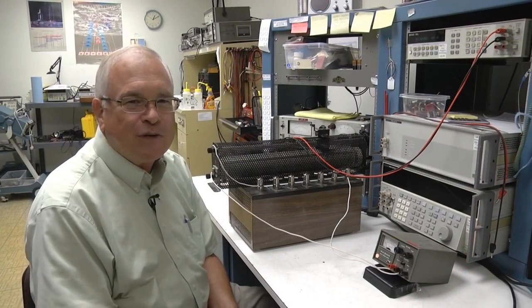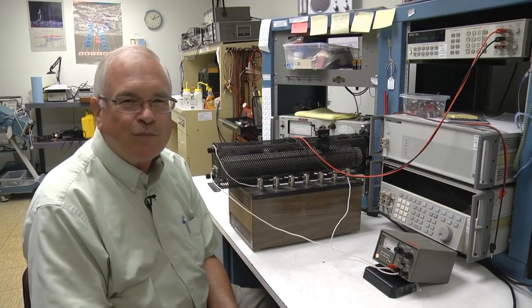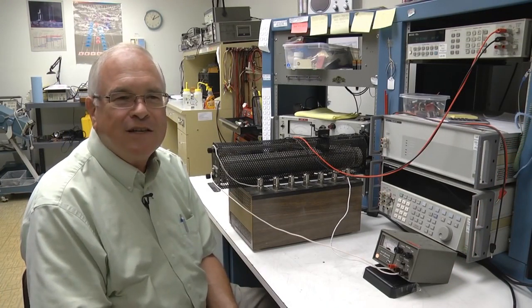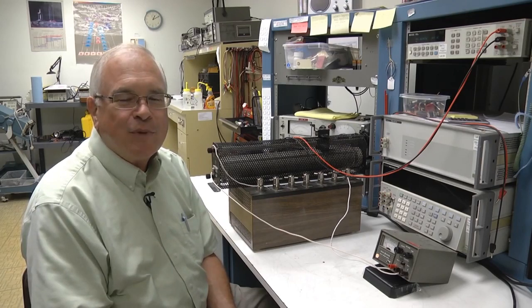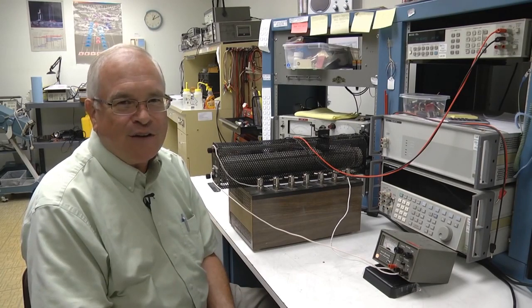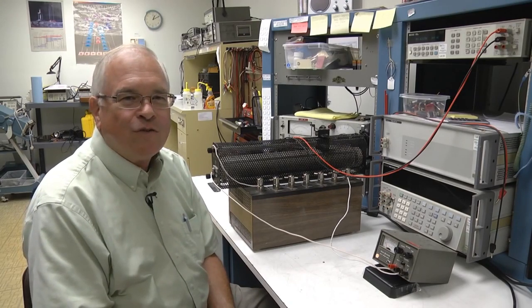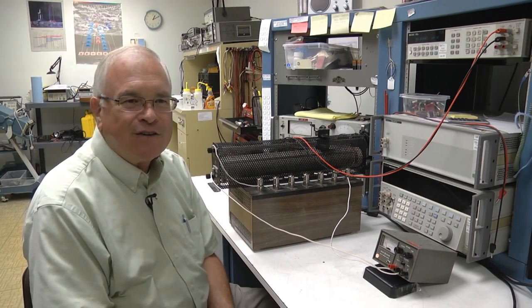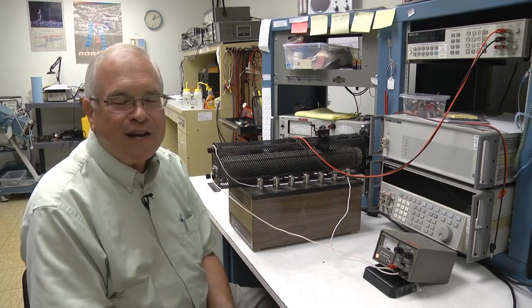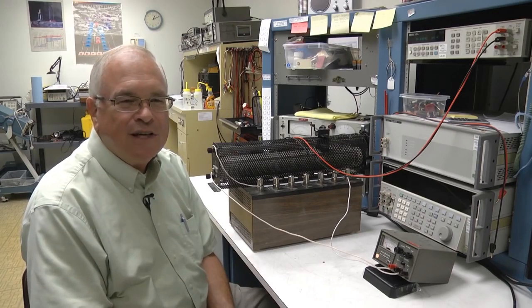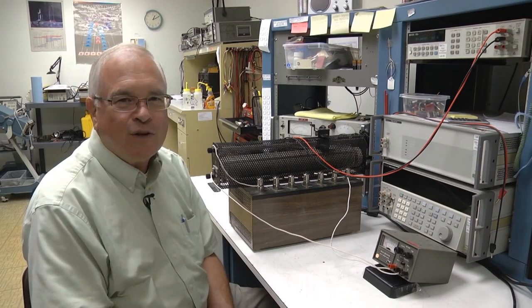This concludes the calibration process for general purpose DC power supplies. What we've checked is the panel meter, either digital or analog depending on the meter, for voltage accuracy, and we've also checked the panel meter for current accuracy. We've also checked for AC ripple under load, and we've checked for AC ripple under no load conditions.